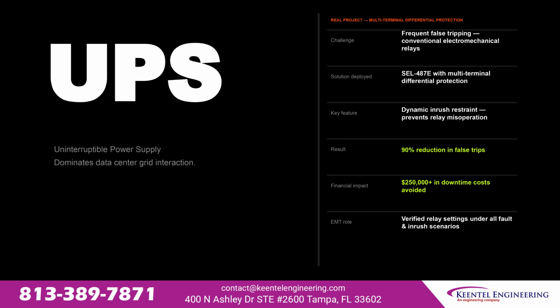UPS systems dominate data center grid interaction, and they're the source of one of the most common EMT study findings. Real project, a multi-terminal differential protection problem. Conventional electromechanical relays were causing frequent false tripping, disrupting operations, and accumulating downtime costs.